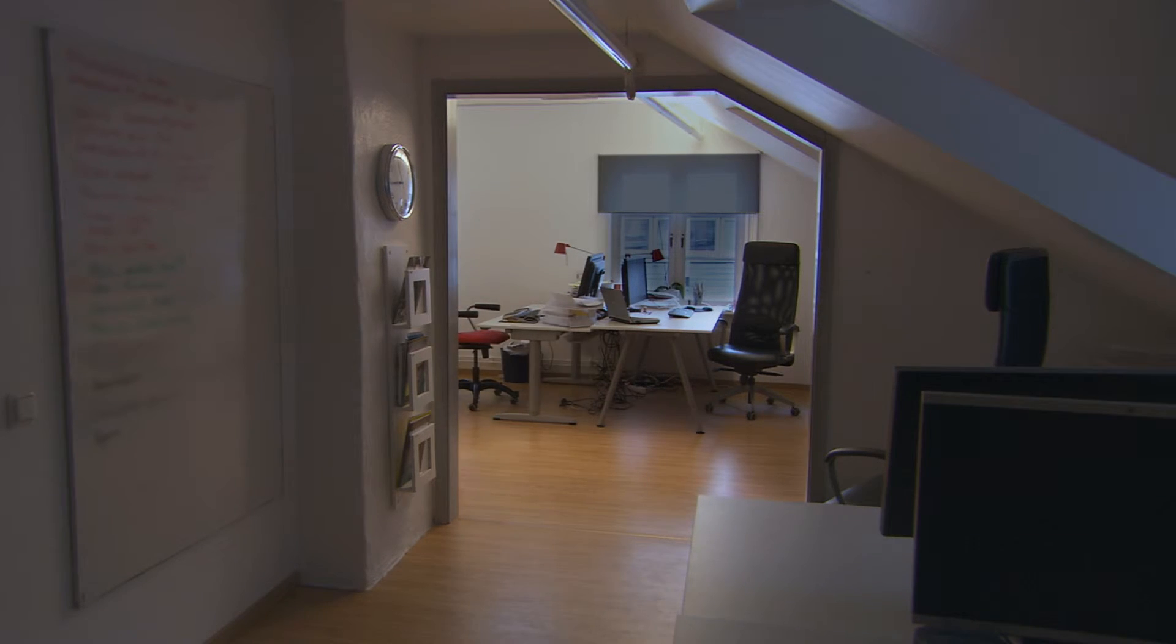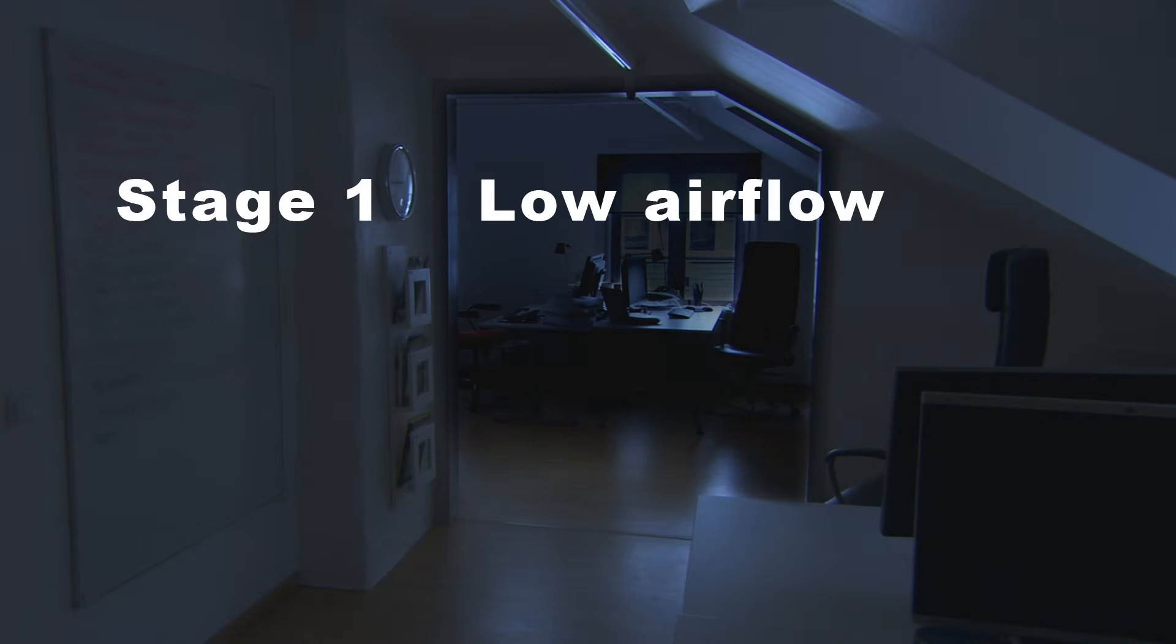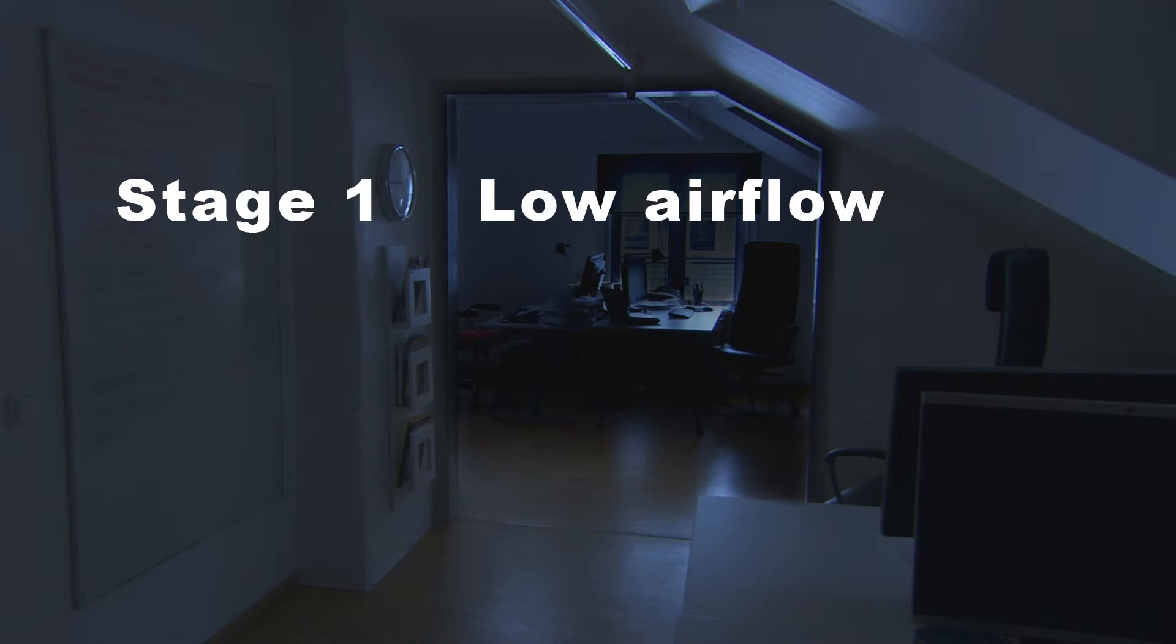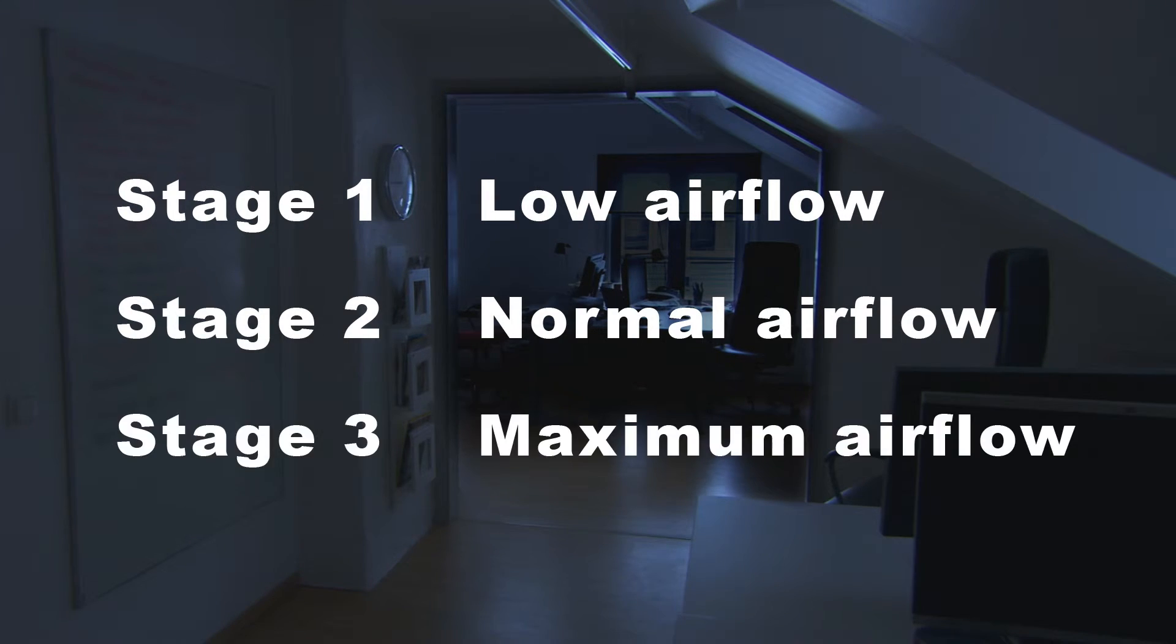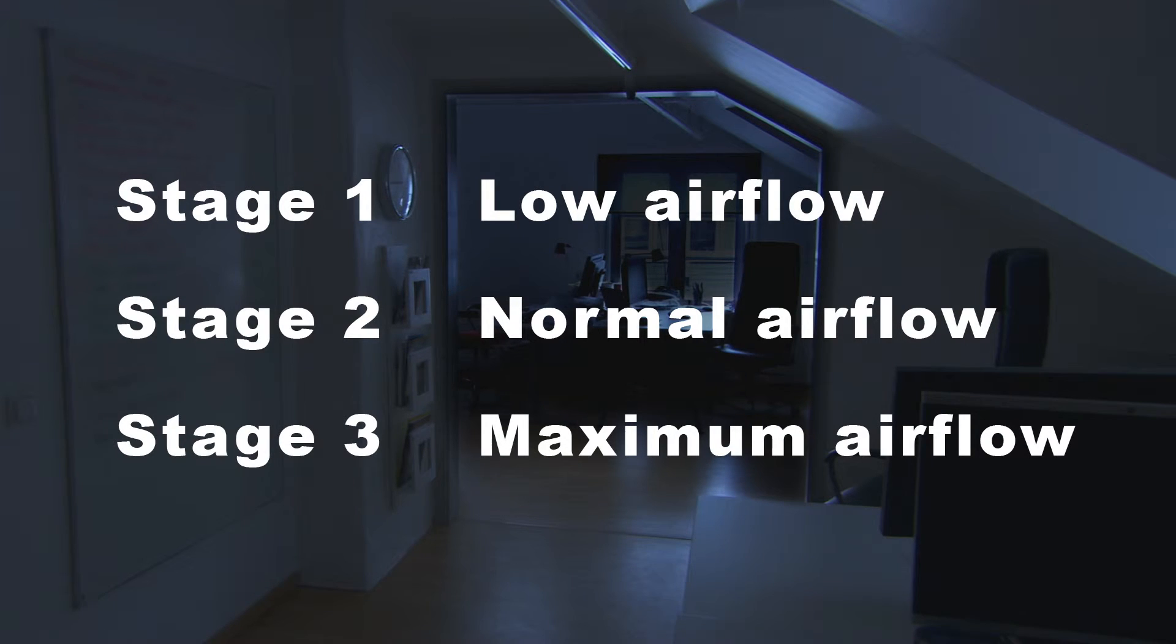The preset values are that stage one has a low airflow. This must always be the lowest set value. Stage two is for normal use and stage three is with maximum airflow. Stage three must always be the highest or at least similar to stage two. You will select the stages when you create your time control schedule.